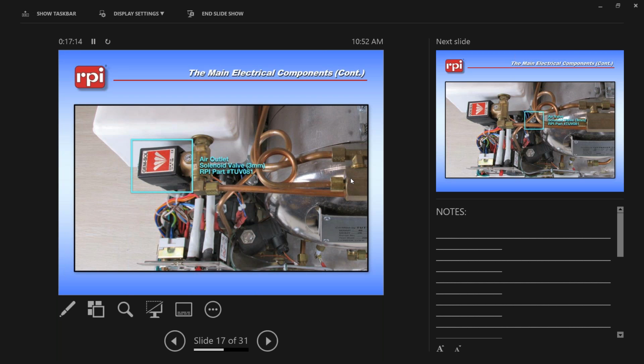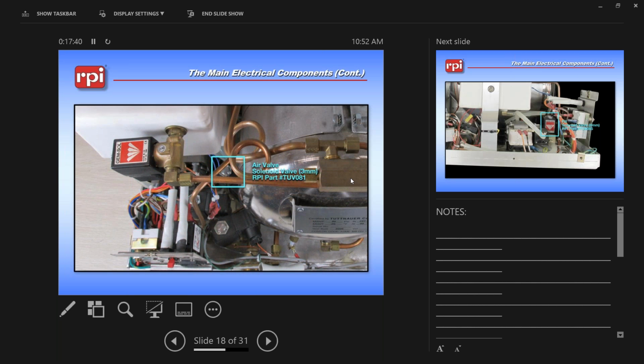Next is your air outlet valve. This is right on the back of your actual reservoir tank. This particular solenoid is the one that acts almost as a bellows on newer style units. It's going to close at 194 degrees Fahrenheit and allow you to build pressure. Up until that point, it's just relieving cold air. Way in the back there is the air valve, which basically just opens up and allows the air compressor to put air inside the chamber for closed door drying.